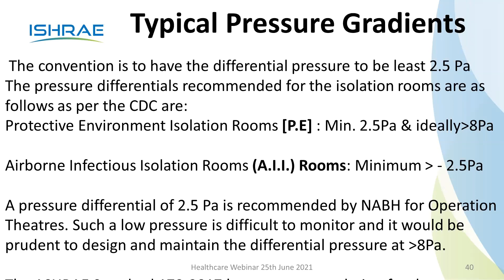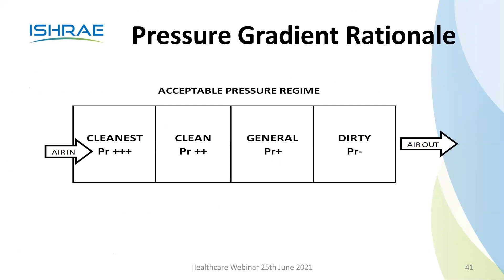So now the pressure gradient rationale is like this. The cleanest area is kept at the highest pressure. From there it exfiltrates to the clean areas, then to the general area, then the dirty area, and from there it goes out. So if you see, for example, an OT suite, you'll find that you've got the store first, where they keep the instruments that come from the CSSD, the Central Sterile Store Department. That is the cleanest.